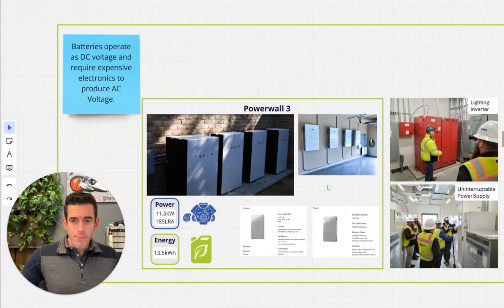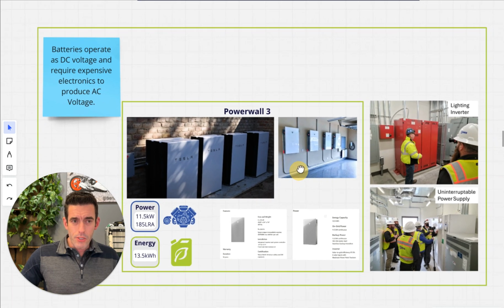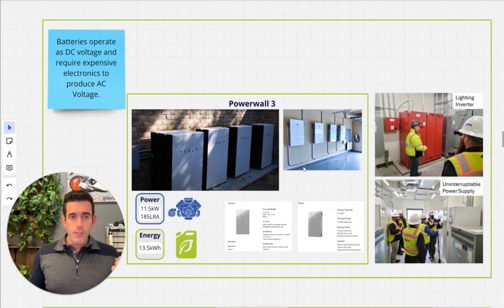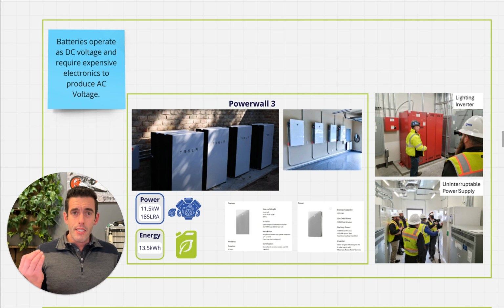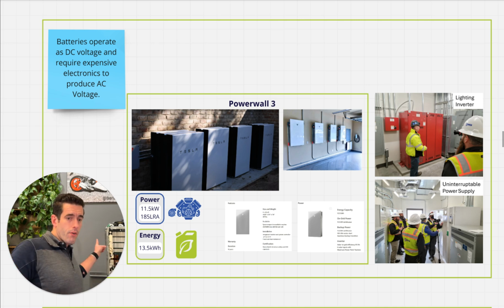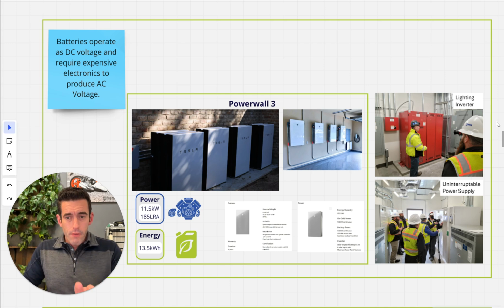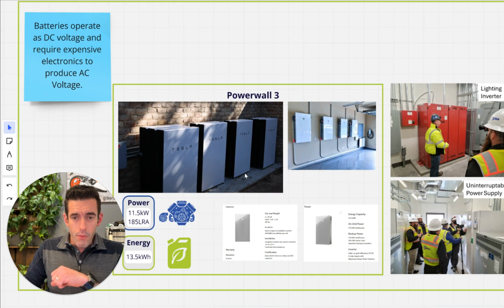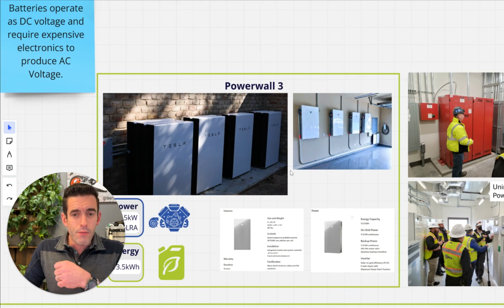So we've got a couple of challenges. First, batteries operate as DC voltage and require expensive electronics to actually produce AC voltage, because they're DC devices and need AC components to change it. I've got one behind me, a UPS power block or inverter. This example here is the Powerwall 3, available for residential or commercial use. With that you've got a big battery and then inverters inside. The inverters are the expensive part.